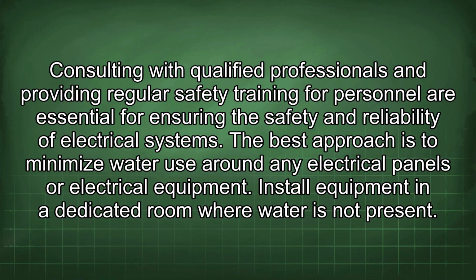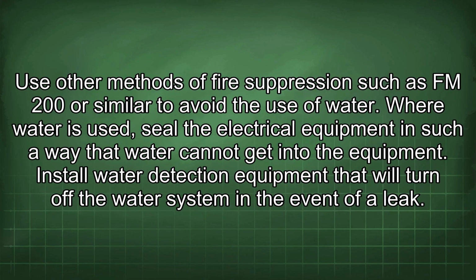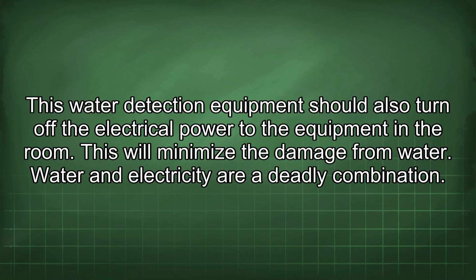The best approach is to minimize water use around any electrical panels or electrical equipment. Install equipment in a dedicated room where water is not present. Use other methods of fire suppression such as FM200 or similar to avoid the use of water. Where water is used, seal the electrical equipment in such a way that water cannot get into the equipment. Install water detection equipment that will turn off the water system in the event of a leak. This water detection equipment should also turn off the electrical power to the equipment in the room. This will minimize the damage from water.